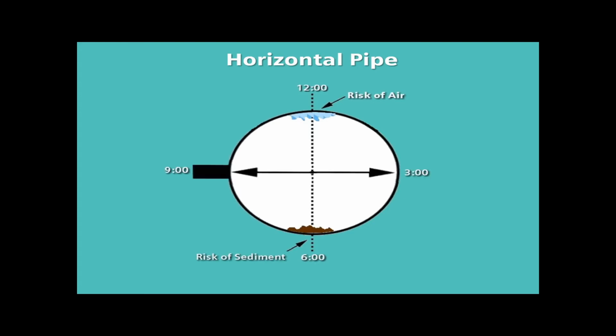Mounting your transducers on the horizontal center line, or at either the 9 o'clock or 3 o'clock position, will provide the best location on the horizontal pipe and avoid the potential of seeing any air which would rise to the top or sediment which will settle to the bottom. The flow sensors can actually be mounted at any angle around the circumference of the pipe as long as you avoid that 12 or 6 o'clock position.